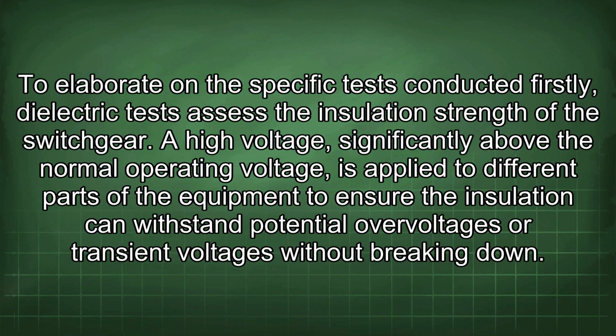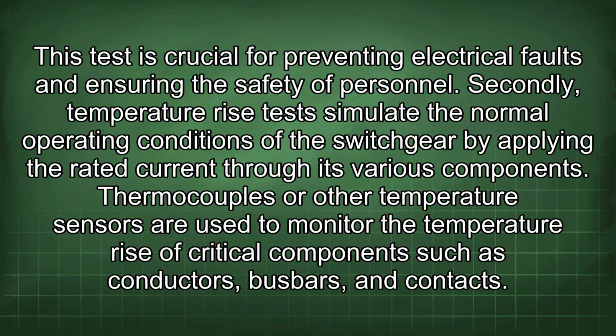To elaborate on the specific tests conducted, firstly, dielectric tests assess the insulation strength of the switchgear. A high voltage, significantly above the normal operating voltage, is applied to different parts of the equipment to ensure the insulation can withstand potential overvoltages or transient voltages without breaking down. This test is crucial for preventing electrical faults and ensuring the safety of personnel.